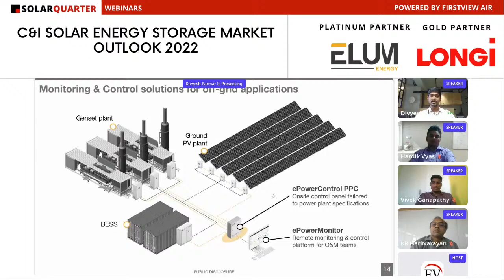So EPower Controller PPC, which is our PPC controller, is basically communicating with these devices over Modbus RTU and/or TCP. And the control philosophies or operating philosophies are based on the technical specifications provided by the end client or the IPP. And some custom logics can also be incorporated. So in terms, we are the vendor agnostic solution provider, which is taking care of the maximum PV output, curtailments of the PV, genset start stop, as well as the charging and discharging based operation philosophy of the plant.